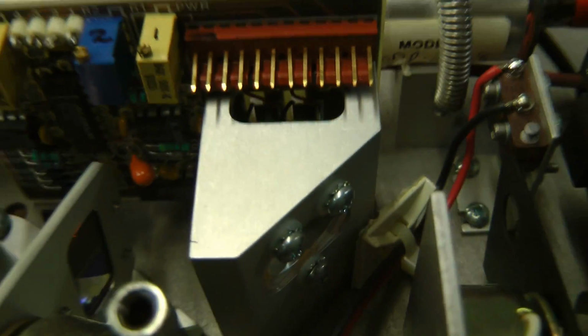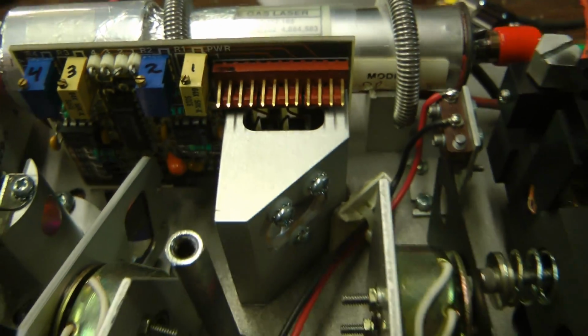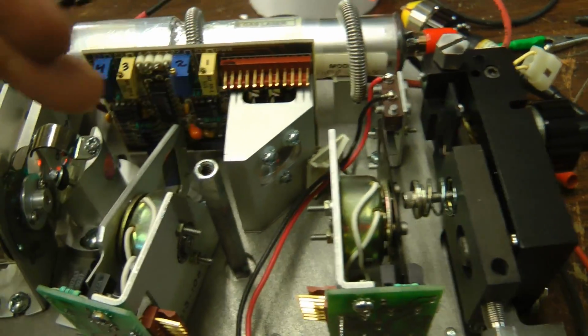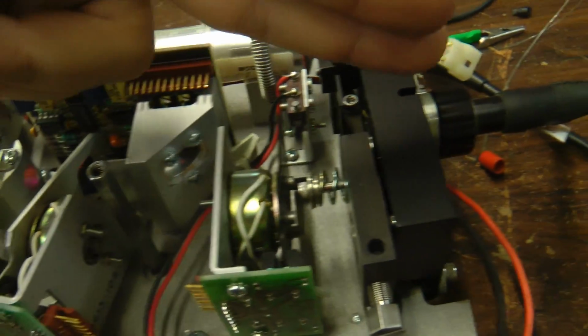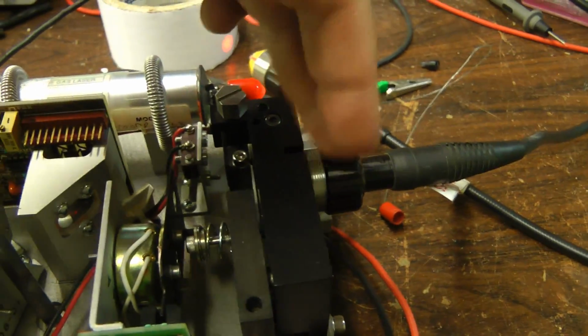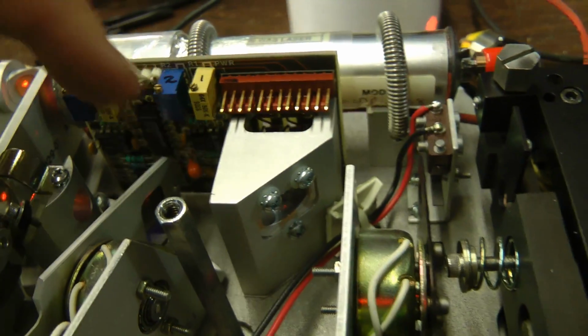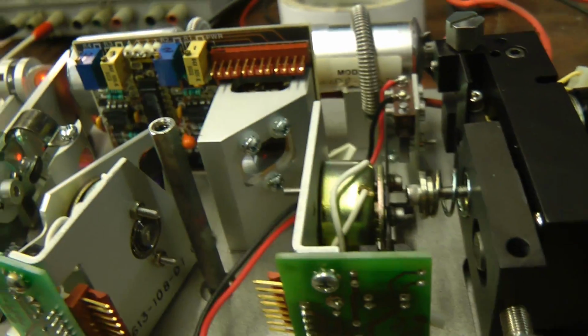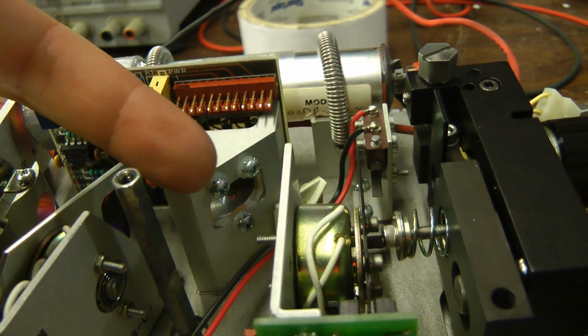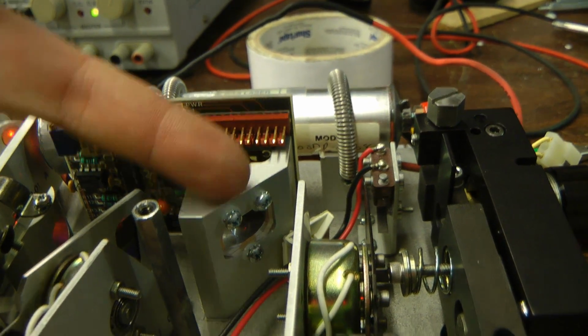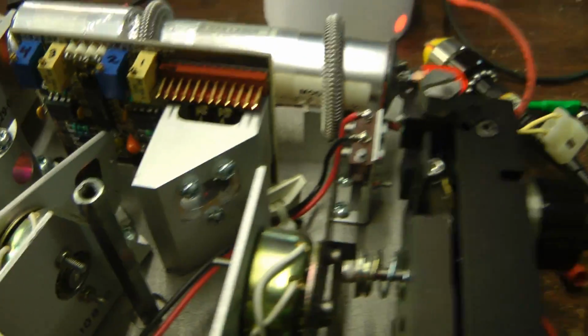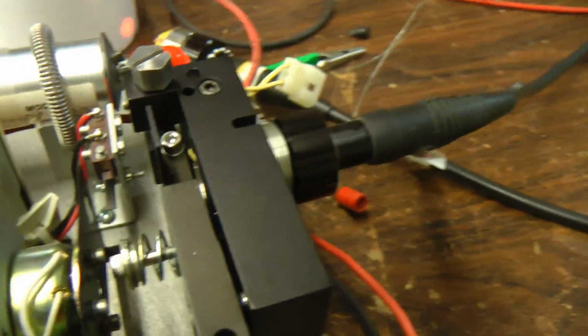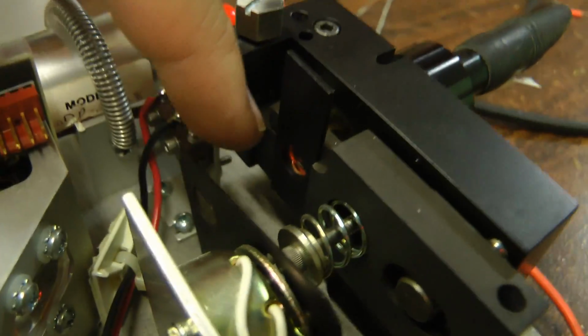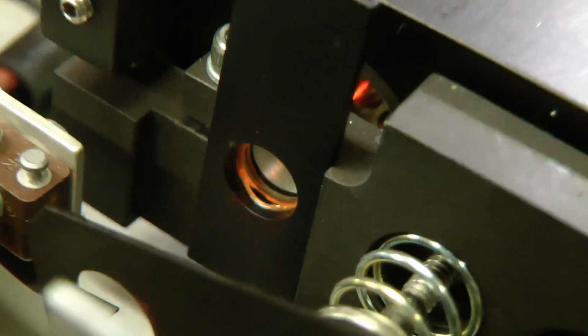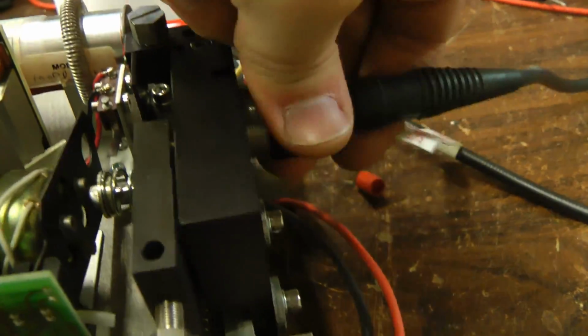I'm curious as to why there's two, because as far as I understand it, the aiming beam and the argon beam have to be exactly in parallel so that they will go through this lens and enter the fiber properly. But I'm not sure why there's a second photodiode there. Perhaps something to do with the reflections, a second order reflection, or a reflection off the second surface of this mirror. This thing is what couples the beam into the fiber, which is basically just a lens right there that focuses the light down to the exact point of entry of the fiber.